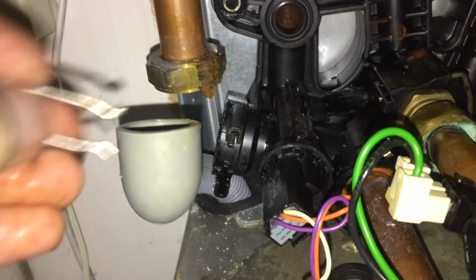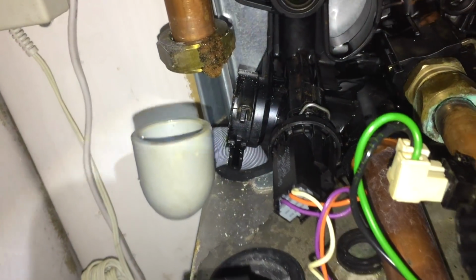Put the clip in. Now, just so you know, if you're working on the Vaillant 837, you can't put this clip in from the top because the plate heat exchanger is that big, it overhangs this. So when you're taking it out, use some long nose pliers and just rip the old clip out, and then in your new pack you get a new clip, you can just put it in from underneath. Saves you having to take the plate heat exchanger off, and it's how the one in my house is. You can see it's quite grubby, this boiler.